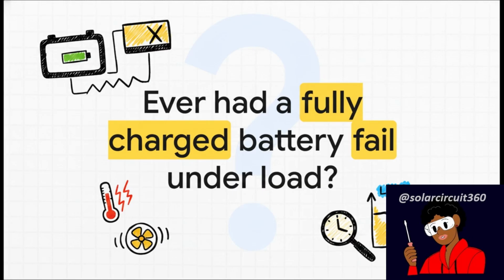Have you ever found a battery that looked totally fully charged on the monitor, but completely gave out the second you put a load on it? What was the clue that tipped you off? Was it the inverter shutting down, some weird heat, or just abysmal runtime? Keep this load testing method in your back pocket, and you'll never be fooled by the resting voltage illusion again.